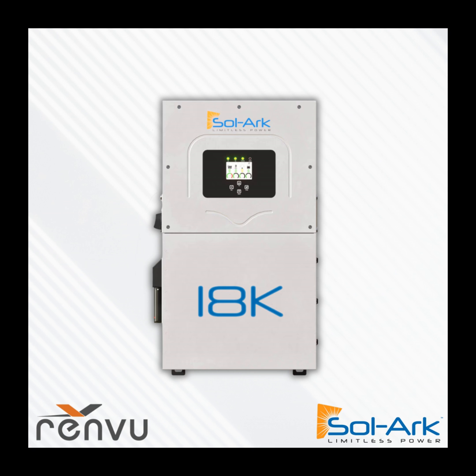To close it out: yes, we have the Sol-Ark 30K for 208 volt. The Discover battery cabinet is only for our 60 kilowatt inverter. On 480 volt, you can do 2 inverters to get more like a 2-hour battery, or 1 inverter for more like a 3.5-hour battery. You can also do 2 battery cabinets for 1 inverter, so if you're peaking into the 7-hour battery duration, you can get there too with our platform.